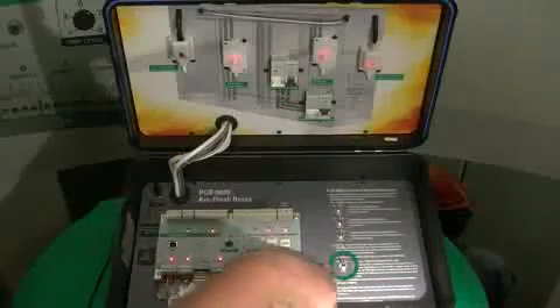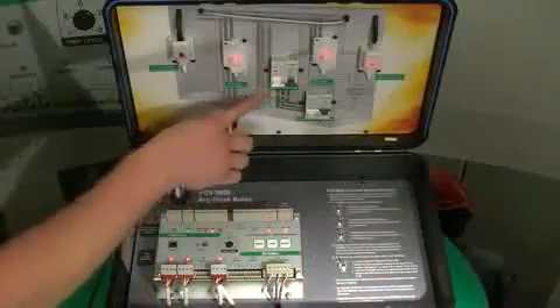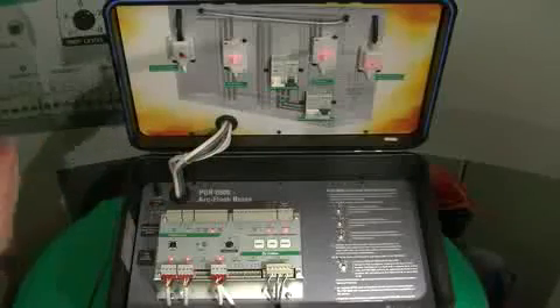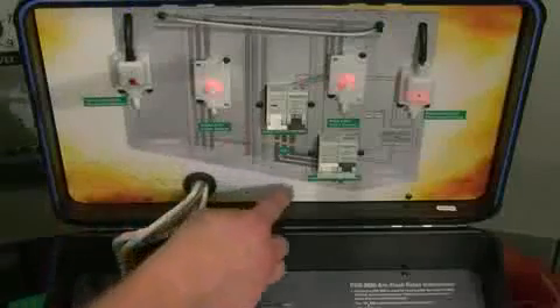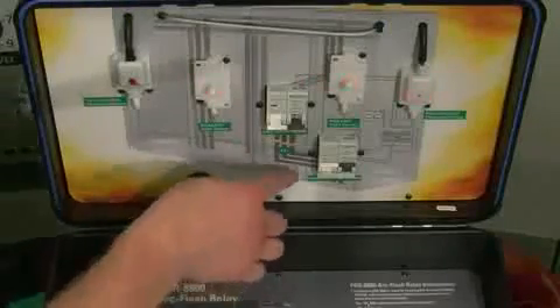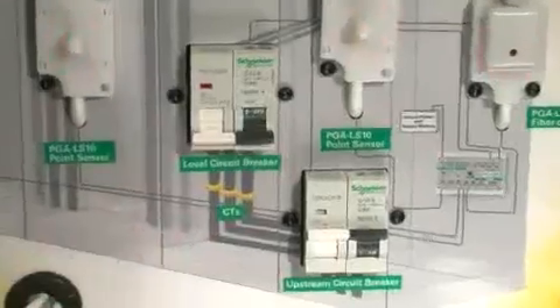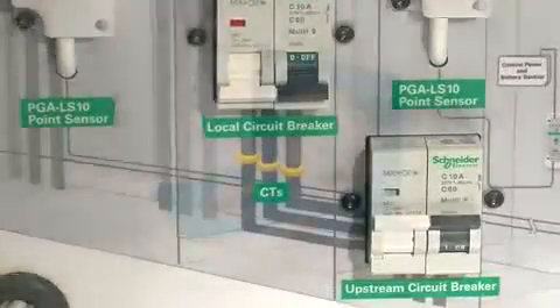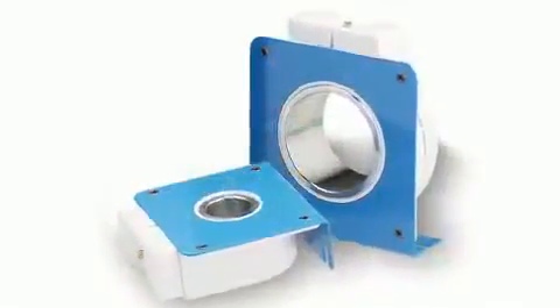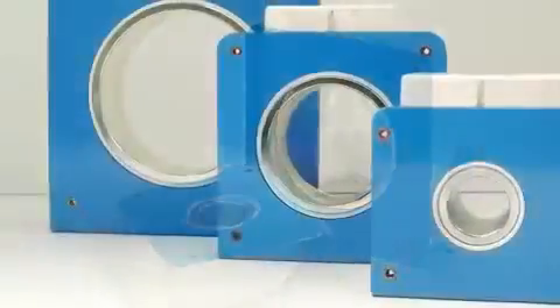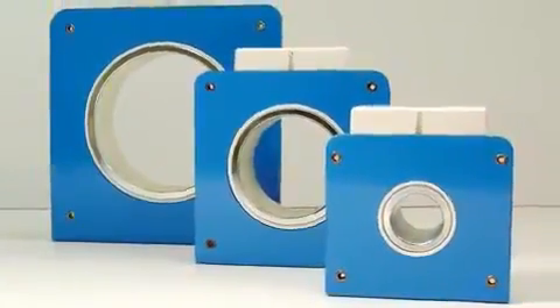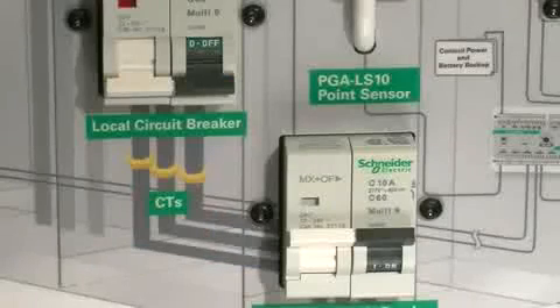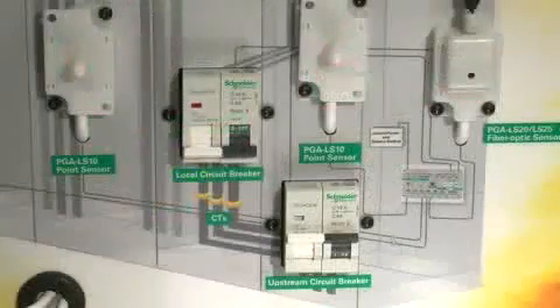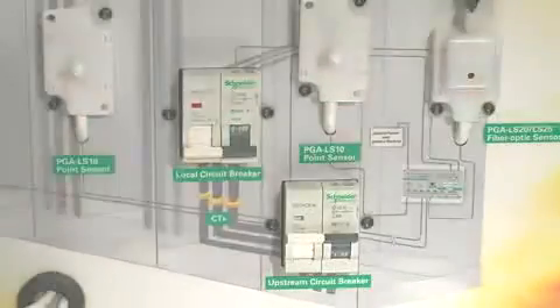If I were to set this in fail mode, it would then bypass breaker 1 because it represented a jam breaker scenario. It would then pass the main breaker and go up to the secondary breaker that was feeding the main. The CTs that you see in the diagram are representative of CTs that can be added to our relay. We would add the CTs if someone had concerns of maybe high ambient light or someone opening a door panel. If the unit sees a flash, it will then ask the CTs if they see an overcurrent. If they see a flash but no overcurrent, the unit won't trip.